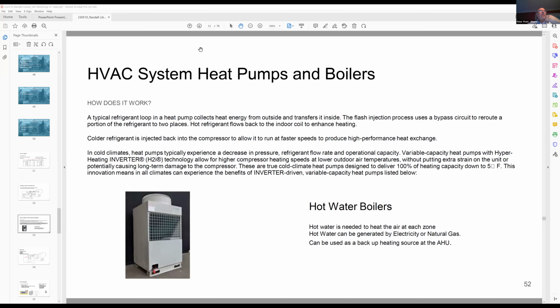We would set it up to be dependent on the temperature and dependent on if there is a failure. If the heat pump fails, you don't have heat into the building. I tell clients all the time, if it fails in the middle of summertime it can be uncomfortable, but with the way we set the strategy up, you have an air handling unit that could provide 100% of air into the space, so you would not have to shut your building down.